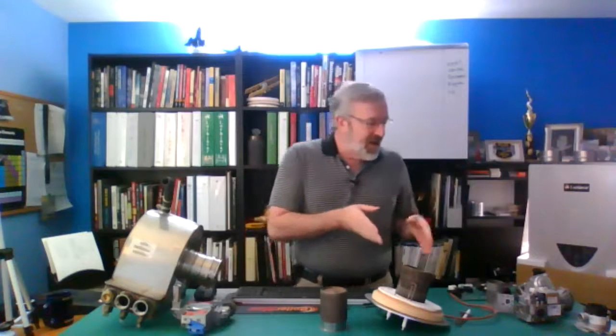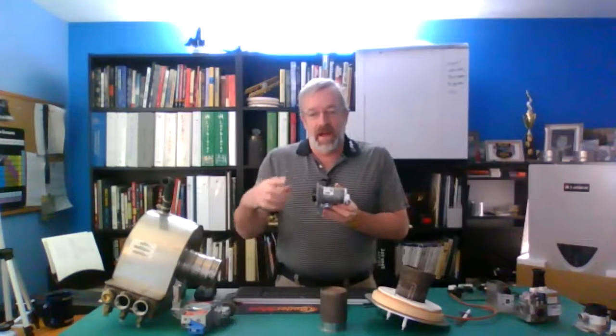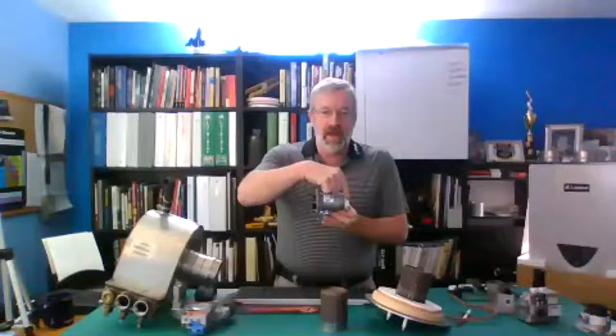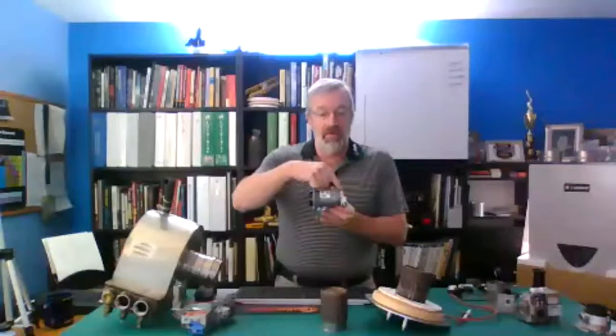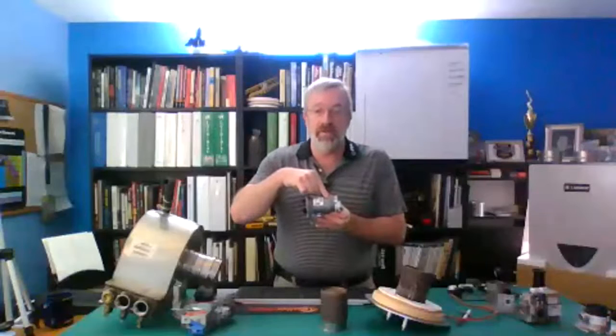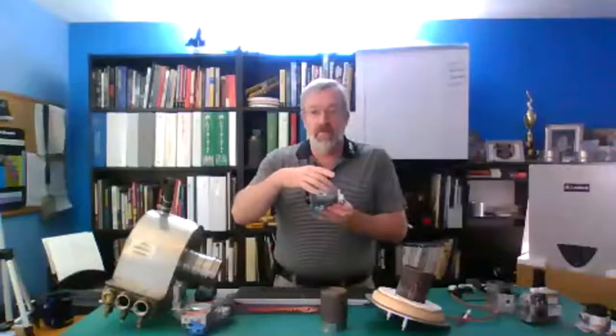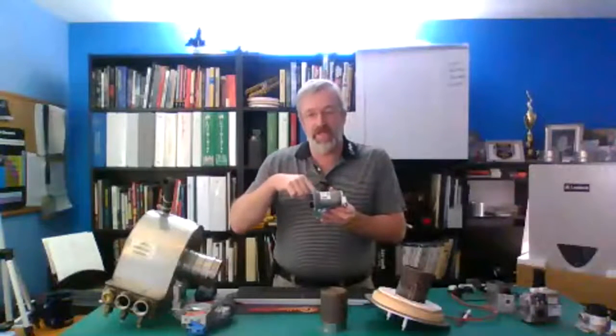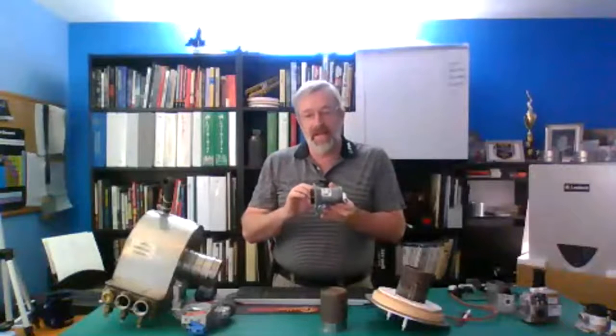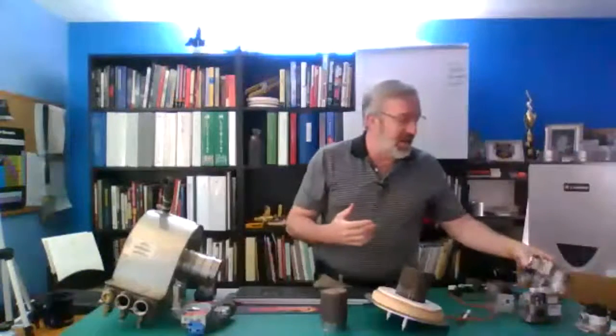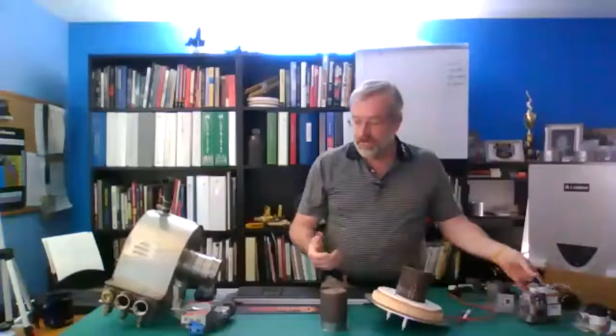So the air is important for a couple of things. If I reduce, go back to this guy here. If I reduce the amount of air I'm pulling here, reduces the amount of air that's going here, reduces the amount of air going across my orifice. Make sense? If I reduce the air across the orifice, I change the air that I'm basically pulling out of my gas valve, okay? So what can impact my airflow?